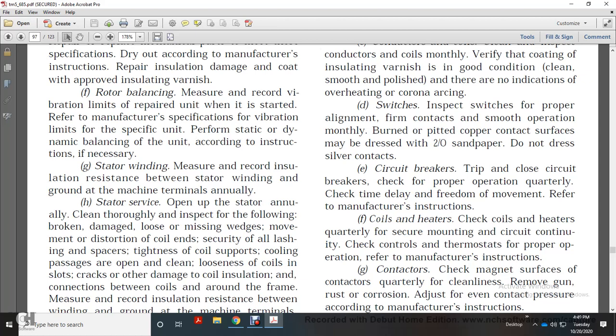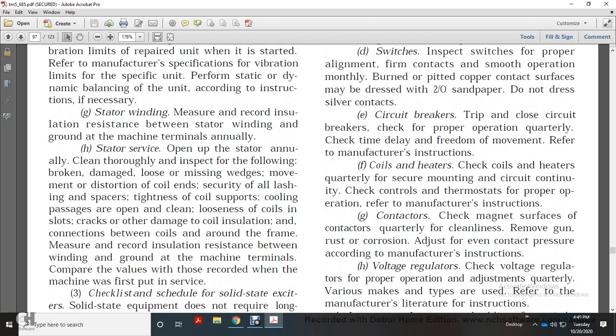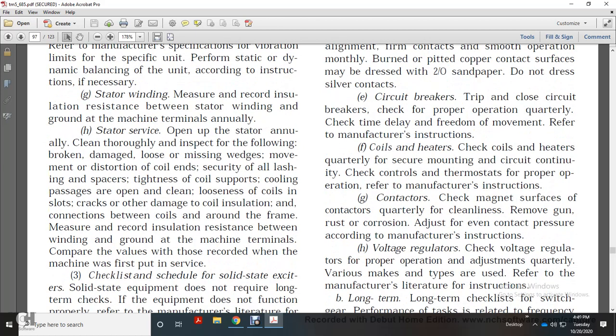Alright, your stator winding. Measure and record the insulation resistance between the stator winding and ground of the machine terminals annually. Service the stator annually, cleaning thoroughly. Inspect the following: broken, damaged, loose, or missing wedges; movable or distorted coils; insecure lashing, spacers, and coil supports; cooling passages open and clean; looseness of coils in slots; cracks or other damaged insulation between coils around the frame.